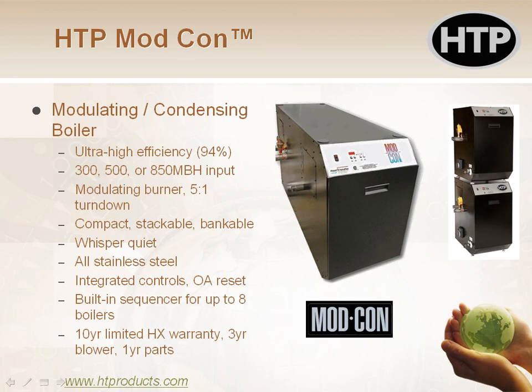But even if there was a loss, or even if it was equal, it's still significantly more efficient than a water heater. Gas burning appliances like furnaces, boilers, and water heaters really don't change efficiency based on the season. But things like heat pumps and air conditioners do because they are rejecting or claiming heat from the outdoors. So that makes a big difference. A boiler is doing his own thing. It's a combustion efficiency thing, and he spits his exhaust outside, and he doesn't really care. He's not grabbing any energy from outside. If I had a heat pump, he's grabbing energy from outside, so the outside air temperature matters. Gas appliances, it doesn't really matter. Let me see if there's any other questions on here.